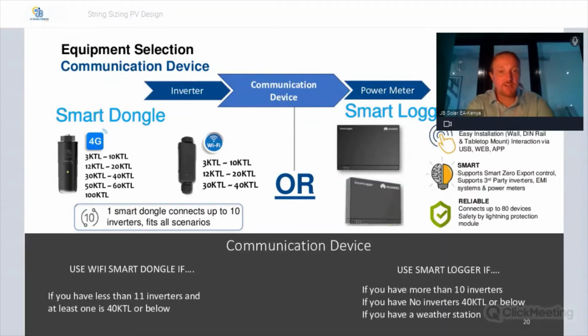So there at the bottom in the gray, I've tried to make it clear. On the left, you can use the Wi-Fi smart dongle if you have less than 11 inverters and at least one inverter is 40 KTL or below, because you only need one inverter to be compatible with the dongle. So you could have 5 pieces of 100 KTL and one piece of 20 KTL, and you can use the dongle to manage all of them. As long as one of your inverters is compatible with the dongle, and as long as there's 10 or less, you can use the dongle. Otherwise, you use the smart logger if you have more than 10 inverters, or if you have none that are 40 KTL and below, none that are compatible. And if you have a weather station, you will need the smart logger.